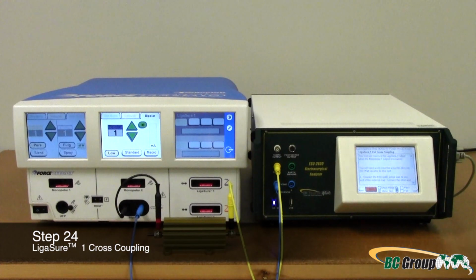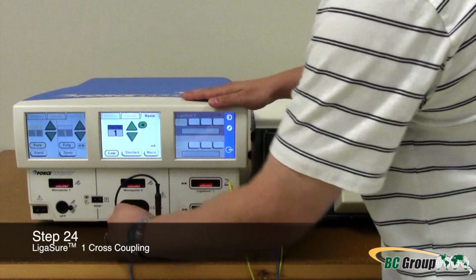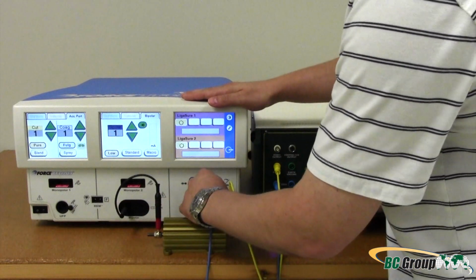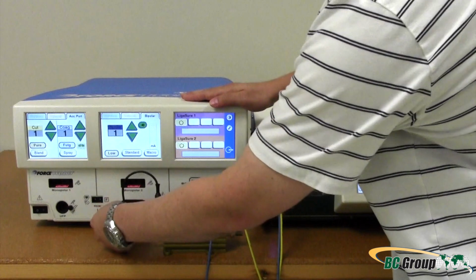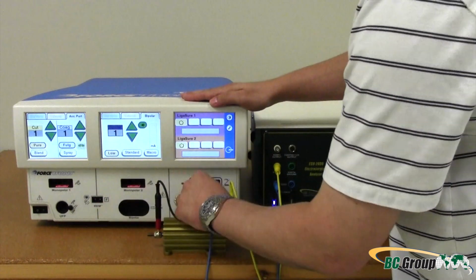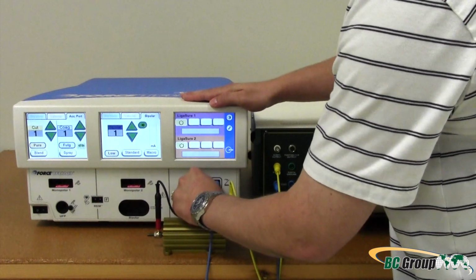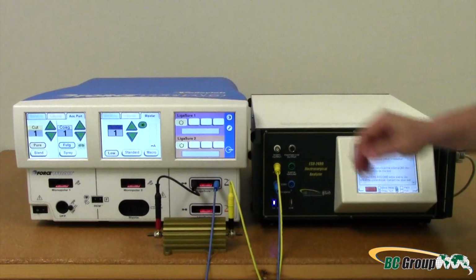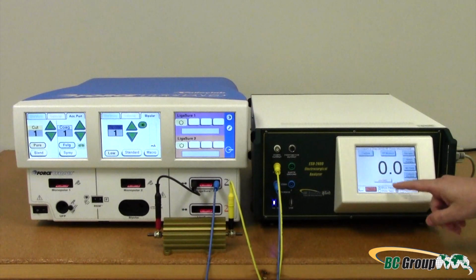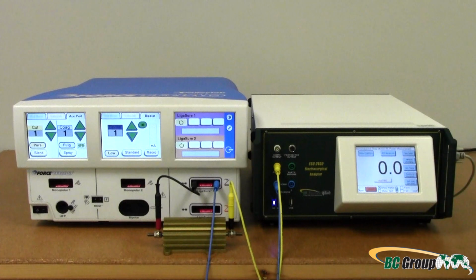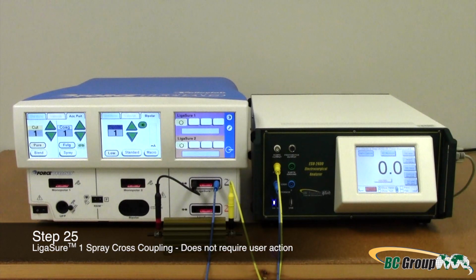Step 24. LigaSure 1, cross-coupling. Move the short jumper lead from the left tine of the bipolar output to the left tine of the LigaSure 1 output. Move the dispersive lead to the right tine of the LigaSure 1 output. Select Show Meter and then press Capture. Step 25 does not require user action.